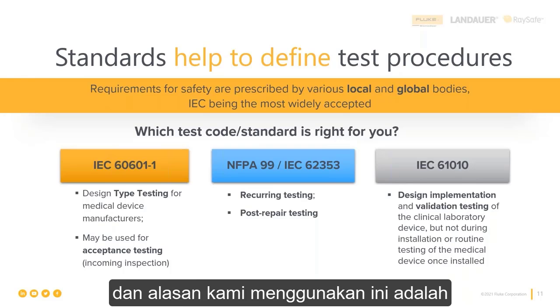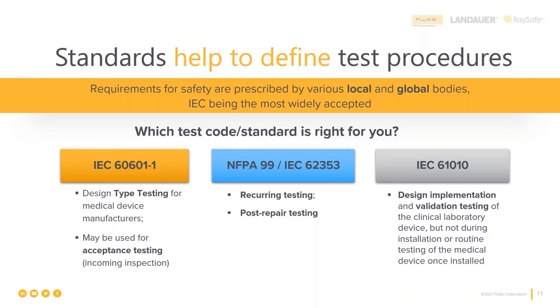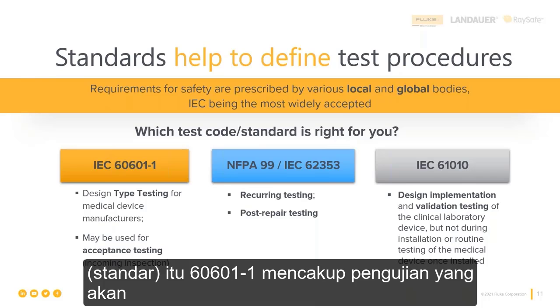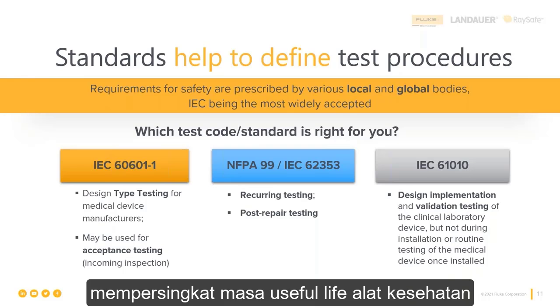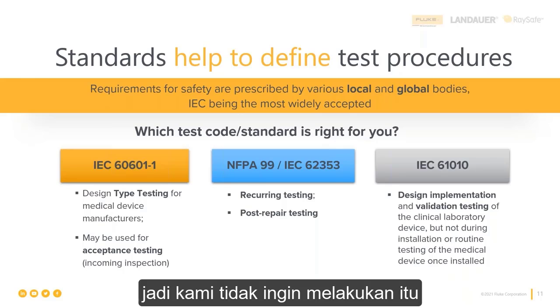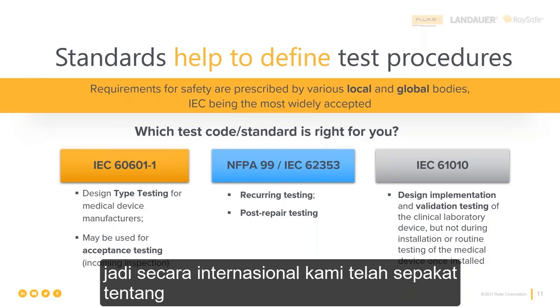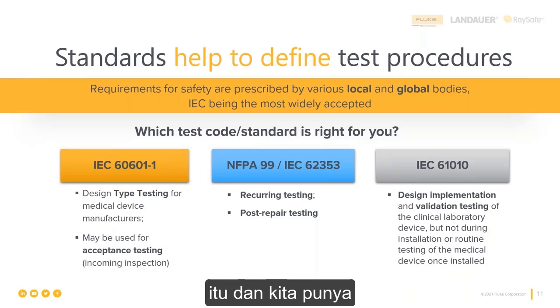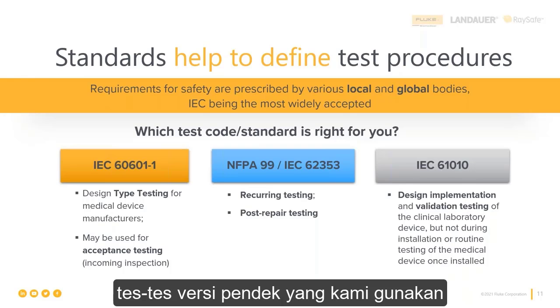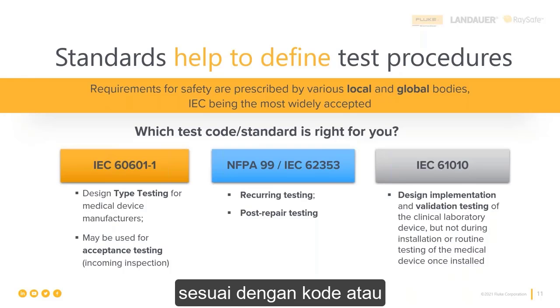And the reason we use these is that the 60601-1 includes tests that would shorten the useful life of the medical device, so we don't want to do that. Internationally, we have agreed about that, and we have these shorter version tests that we use in accordance with whichever code or standard we're going to use.